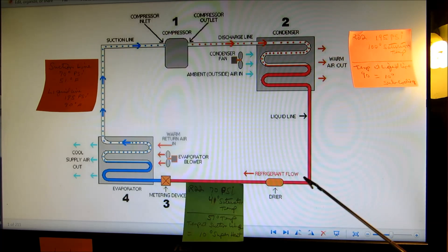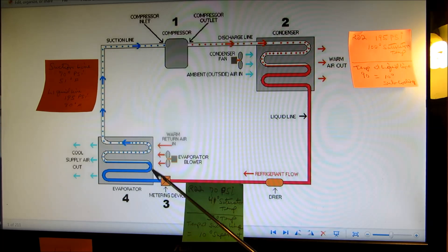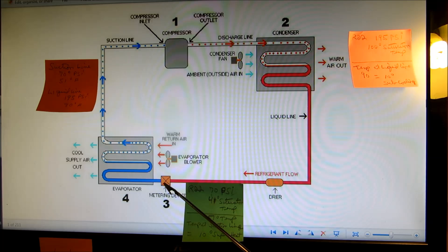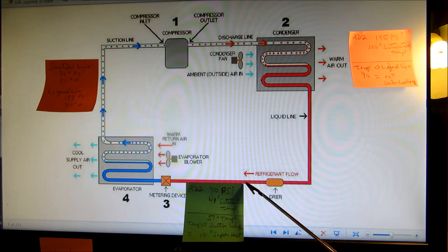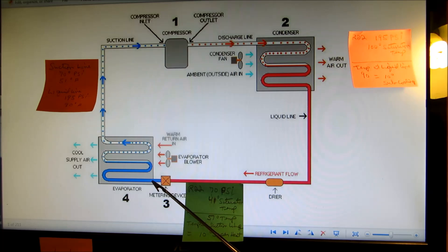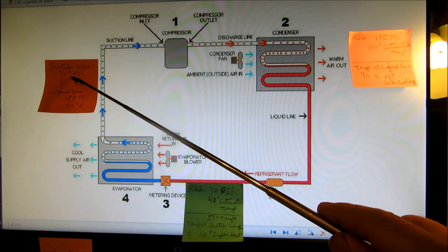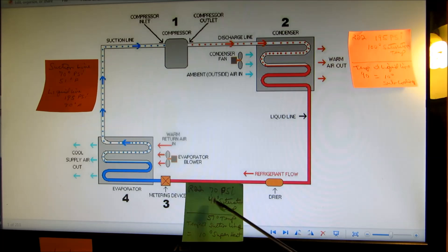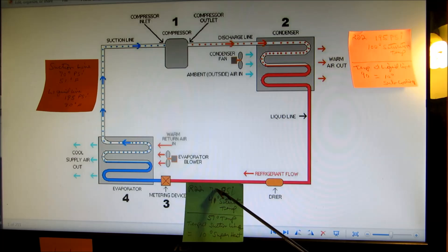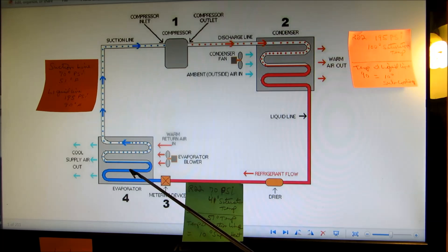We're coming in on the high-pressure liquid line from the condenser after it's been condensed, running up to the metering device. After the metering device — which could be a piston or TXV; in this case a piston, basically an orifice — the low side starts. The liquid sprays in as low-pressure liquid-vapor droplets. At the suction line, 70 PSI gives us a saturation temperature of 41 degrees, so at that blue line we'd read 41 degrees.